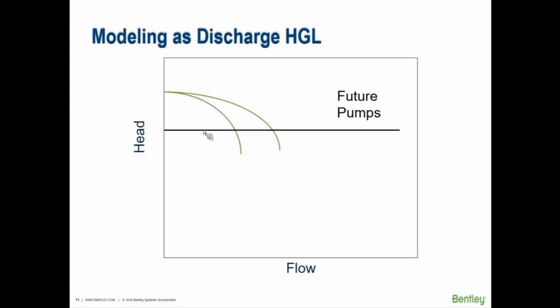You can model a pump as a constant discharge head node — meaning no matter what, the head will always be a certain amount and flow will always be delivered at that rate. This is useful in planning phases when you don't know how many pumps you'll have at the station but know you need to deliver, say, 2,500 gallons per minute. It's a preliminary design approach before actual pump curves are selected.